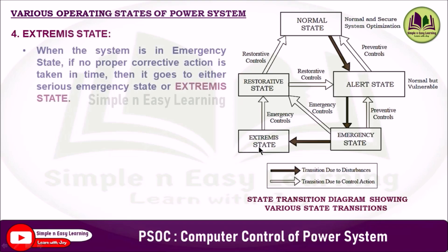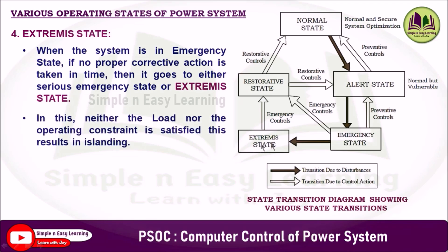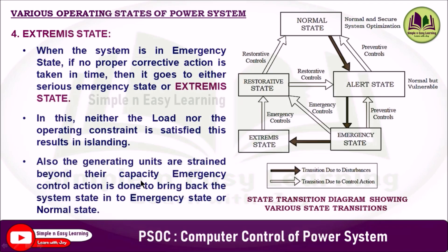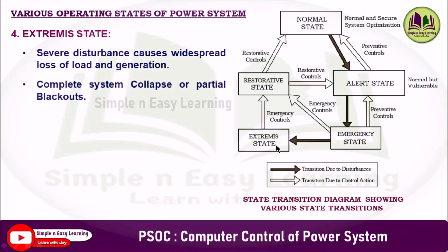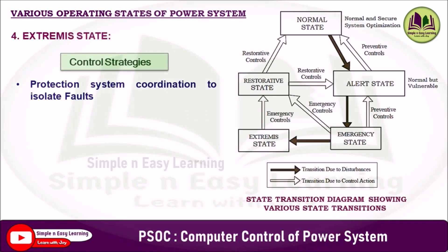The extremis state (also called serious emergency state) is entered when the system is in the emergency state and no proper corrective action is taken in time. In this state, neither the load nor the operating constraints are satisfied, resulting in islanding; generating units are strained beyond capacity. A severe disturbance causes widespread loss of load and generation, leading to complete system collapse or partial blackouts. This state is also called the blackout or collapse state. Emergency control action is taken to bring the system back through the restorative state.